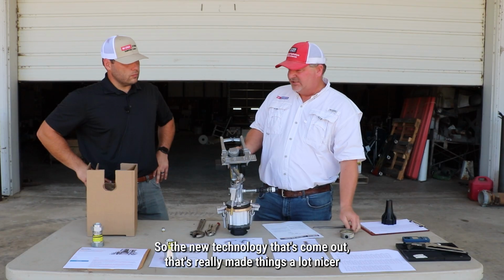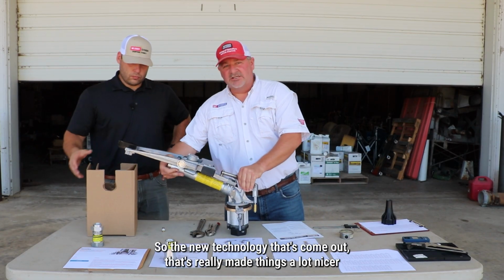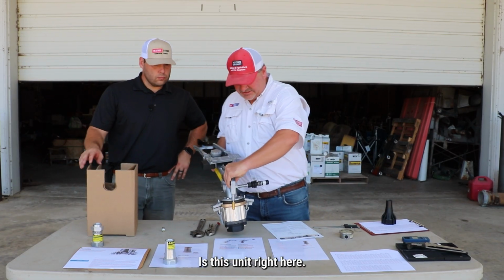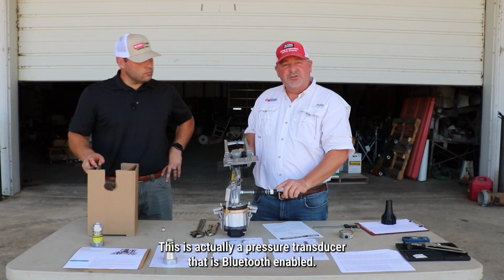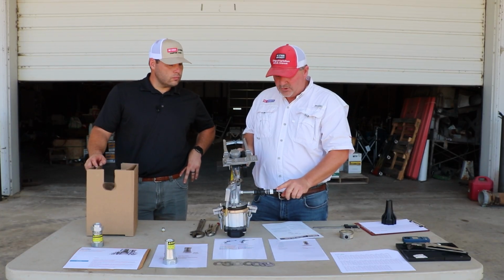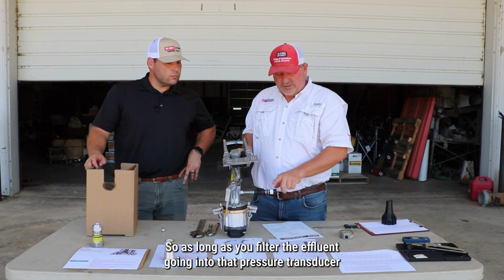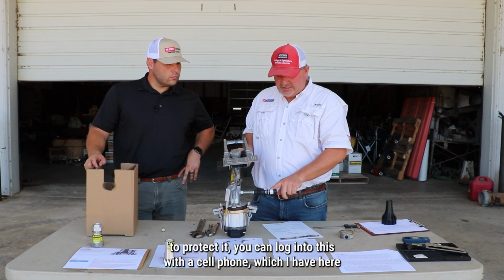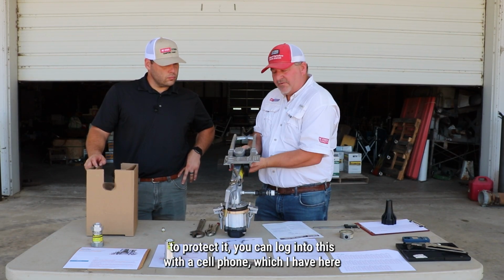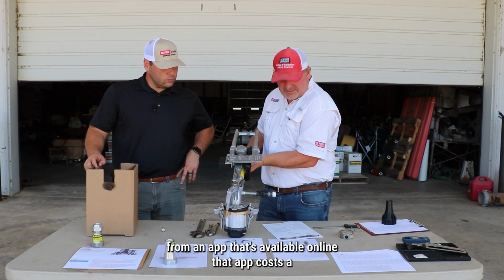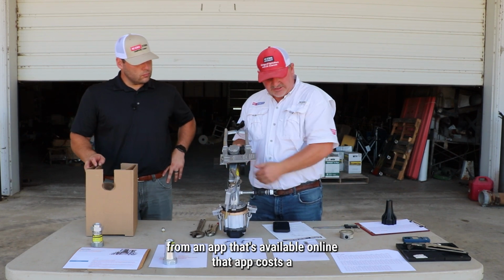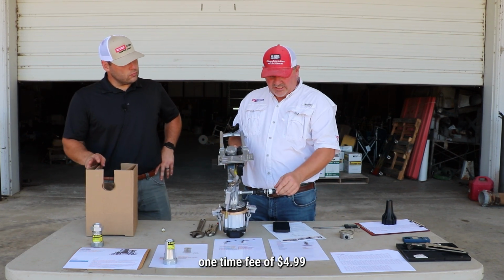The new technology that's come out that's made calibration in the field a lot nicer is this unit right here. This is actually a pressure transducer that's Bluetooth enabled. As long as you filter the effluent going into it to protect it, you can log into it with a cell phone, using an app that's available online.